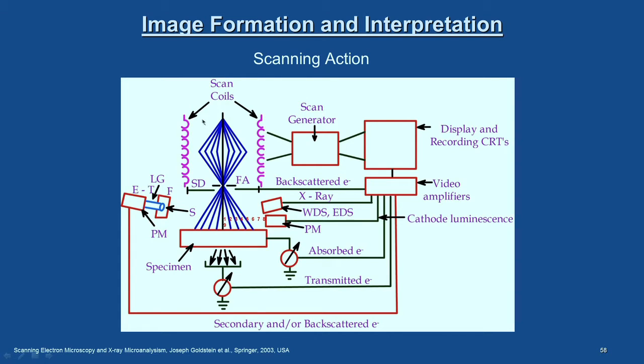What you see here are the scan coils and the electron beam falling on the sample. There is an ET detector — we will see what that is — and the Faraday cage, the scintillator, and the photomultiplier. There is a scan generator and a display and recording CRT, along with X-ray detectors, wavelength dispersive spectrometers, and energy dispersive spectrometers.